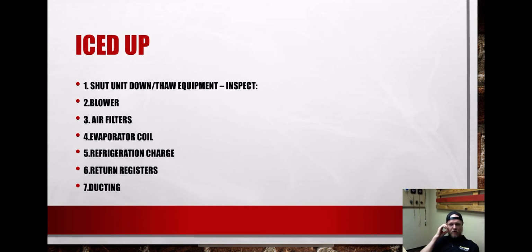So when you go up to a unit and let's say it's iced up, what's your procedures? You got a different procedure for every symptom, right? So you open up the filter panel and you just see a block of ice in between the filters, or God forbid, coming through the filters. First thing you want to do is shut the unit down. You want to inspect your blower. You want to inspect your air filters, your evaporator coil, your refrigeration charge, your return registers, and your ducting.